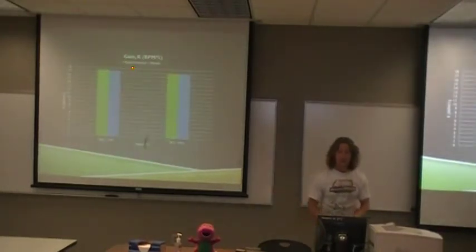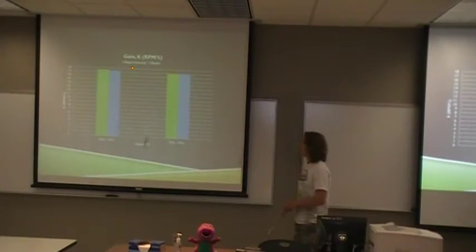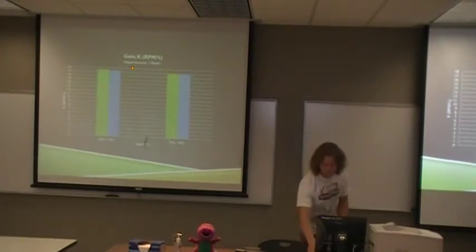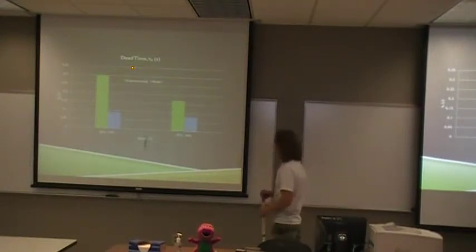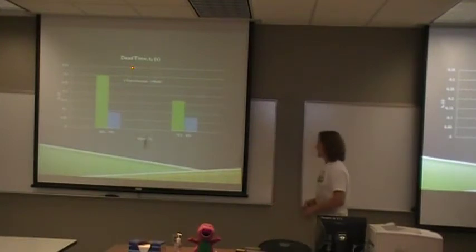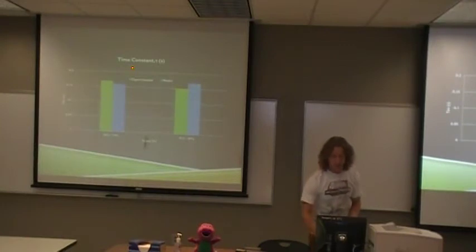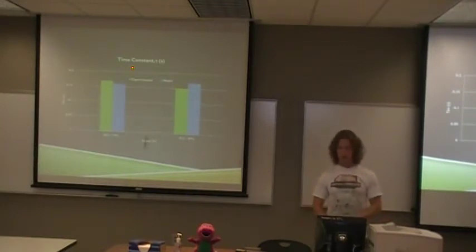Here's a comparison of the gain between the experimental and the model, and they matched up very close. The dead time was a little bit different. The experimental was consistently higher. Time constant, however, matched up pretty close between experimental and the model.